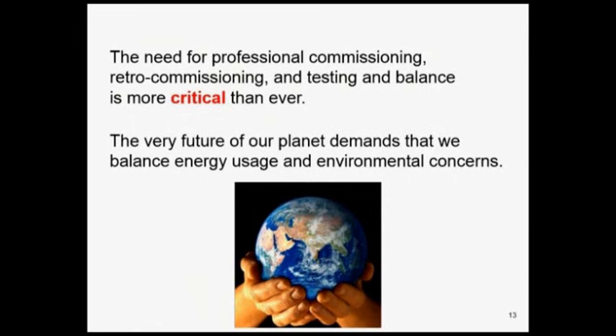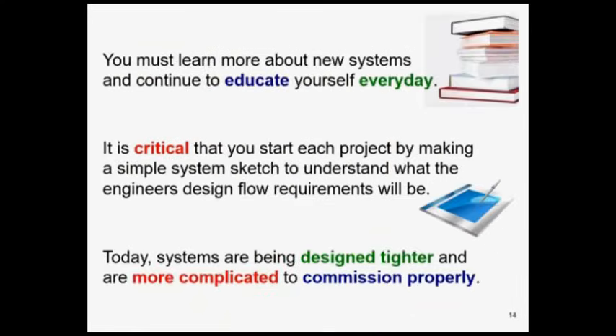So the whole message is it's critical that we commission buildings and we balance them going forward to make sure that we've got the proper balance of energy being used. So what does that mean to you if you're in the balancing business? Systems are changing. The old constant flow systems are gone, and they're variable flow systems. We're trying to take advantage of diversity. You're going to have to educate yourself.